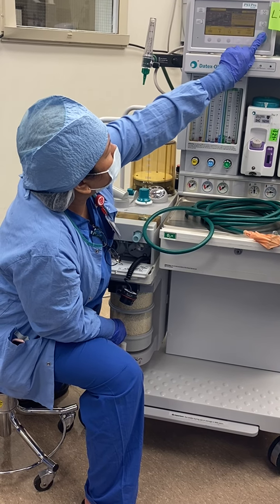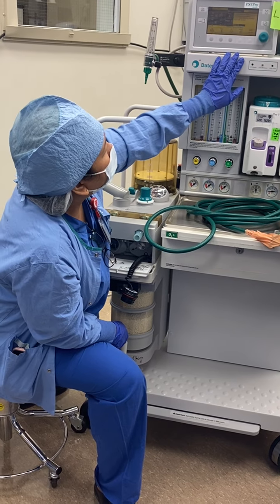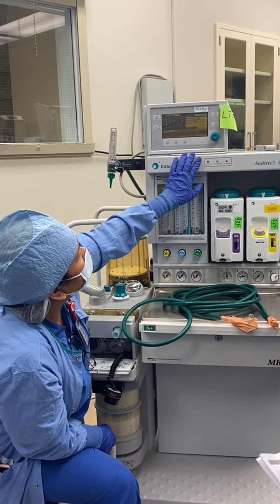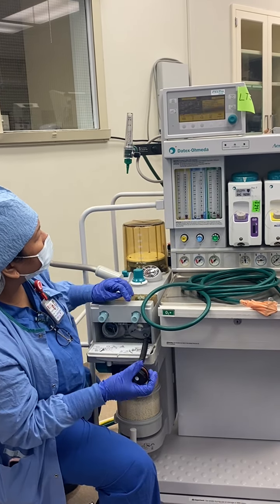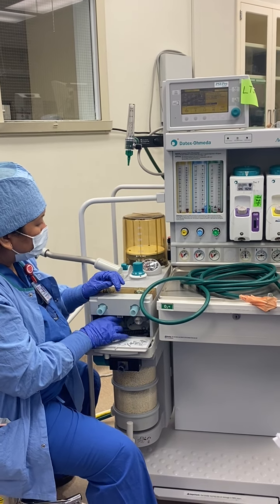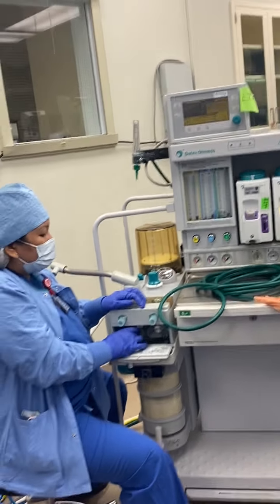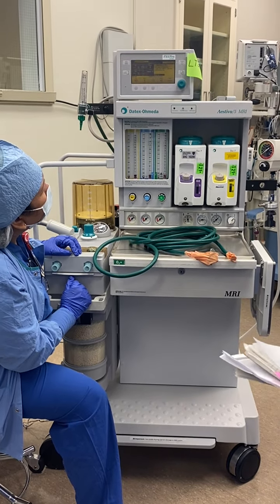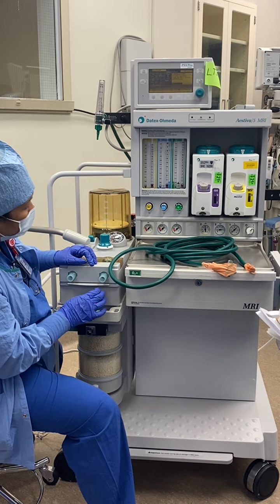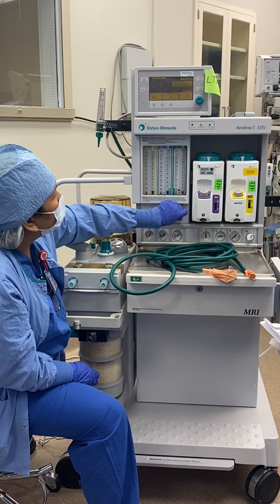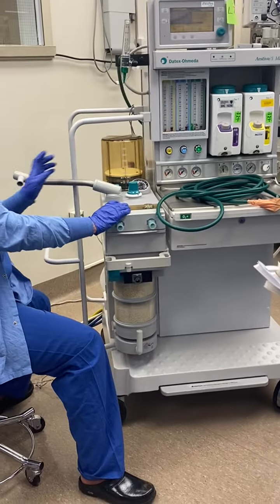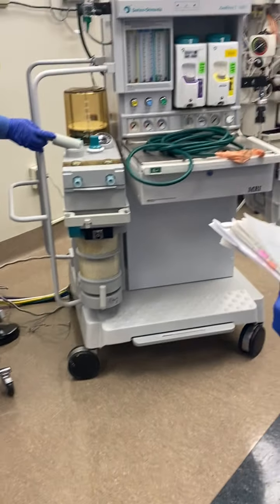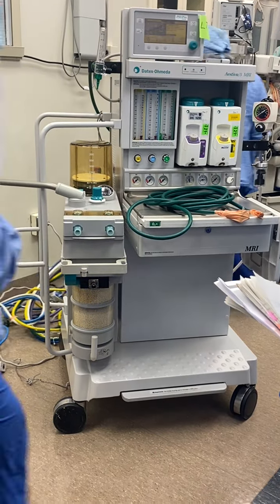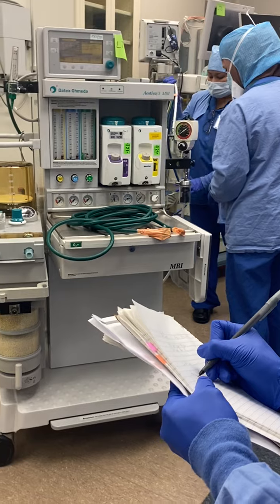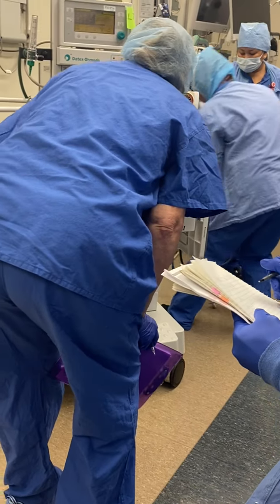Now I'm going to go to 100%. With sensor in breathing system, flow 100% oxygen and then push knob to start. Okay? So it's getting the oxygen directly from the tank, and it's just calibrating what should be 100%? Yes, but it wants you to put 100% here. So we need oxygen. Can we plug in oxygen? I'm working on this machine more because you guys haven't used this machine. I know you guys are used to plugging in oxygen. We'll plug everything in.